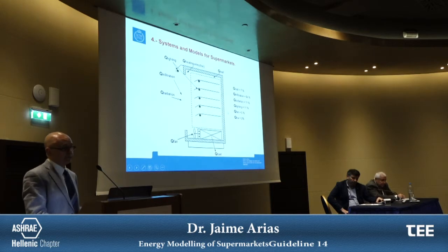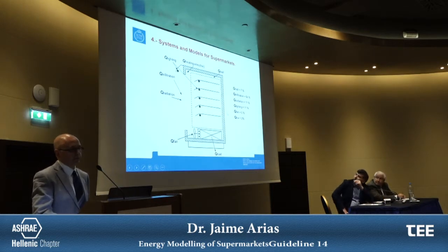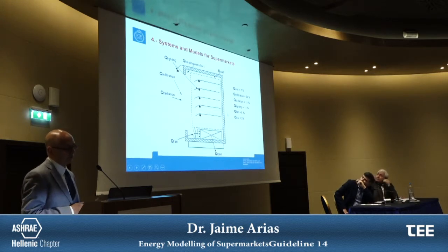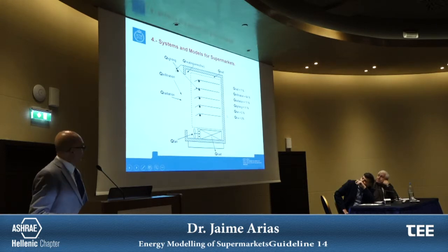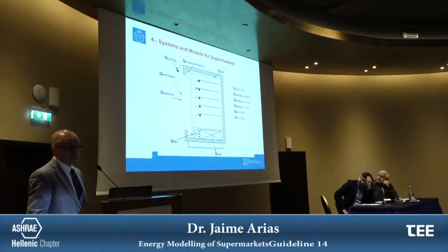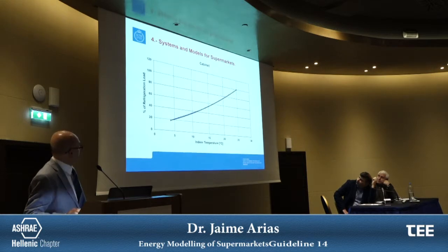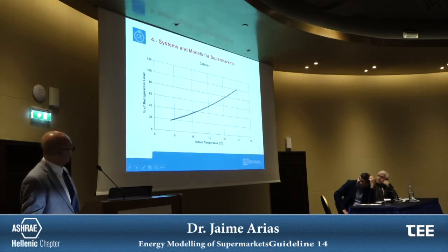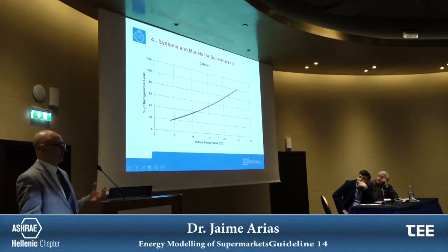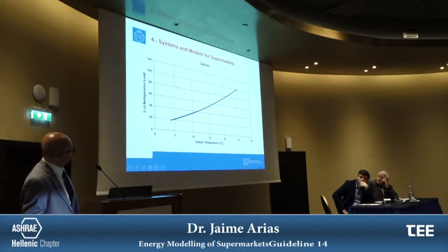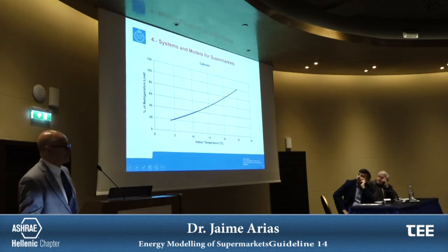For the cabinet, we try to find a heat balance. So here are the different factors: the wall, the infiltration, radiation, lighting, the fans, and this heating wire. And we found a correlation between the indoor temperature and the percentage of refrigeration load. That is this one. So for an indoor temperature of 25 Celsius degrees, you have 100% of the cooling demand for your cabinet. That is the design condition for your cabinet. And if you reduce this, of course, you also reduce the percentage.